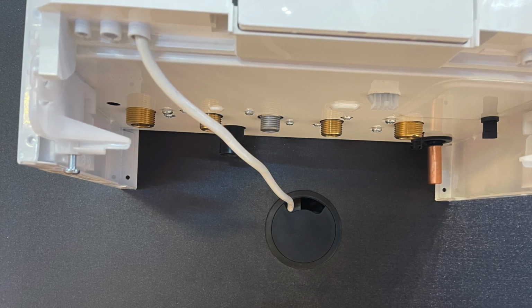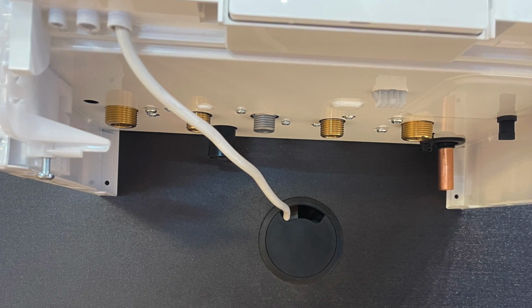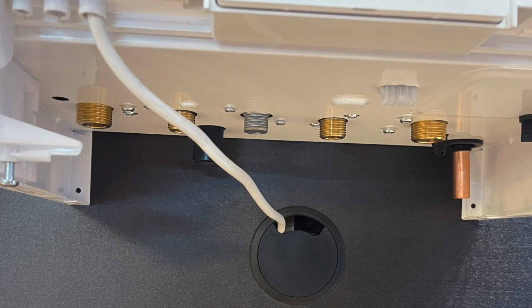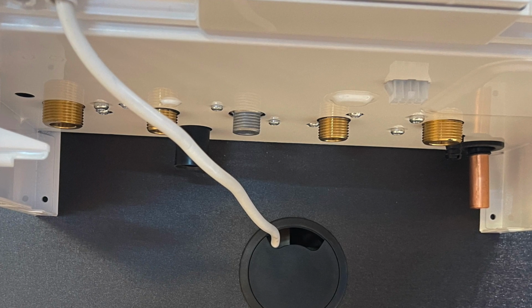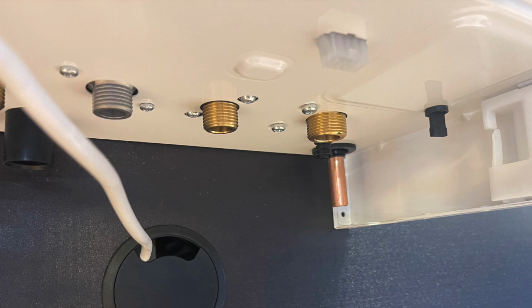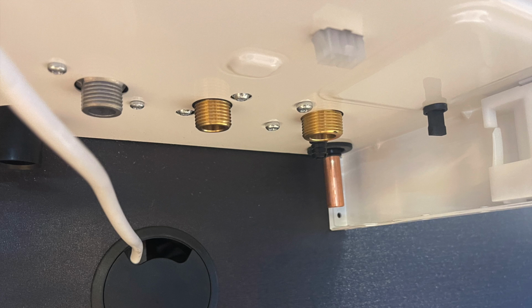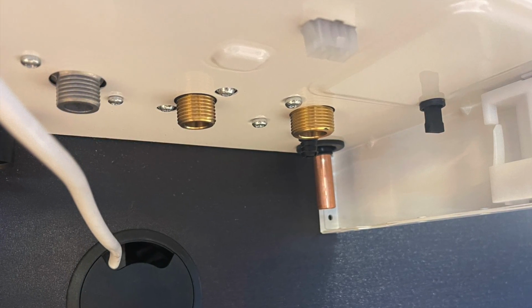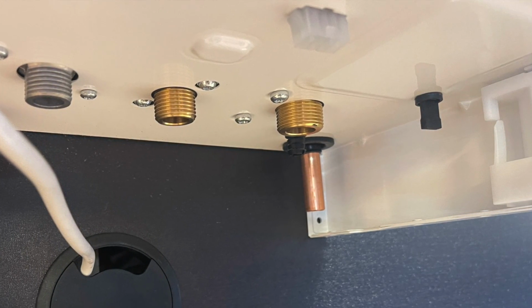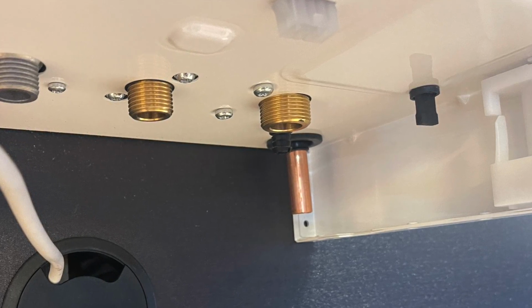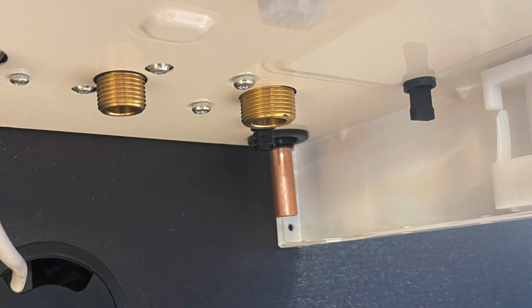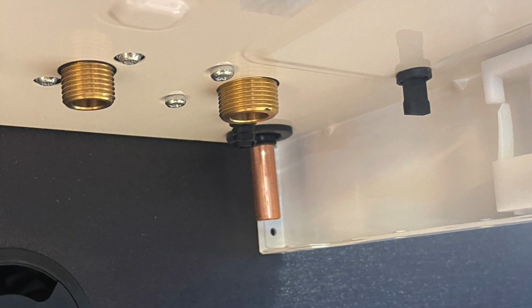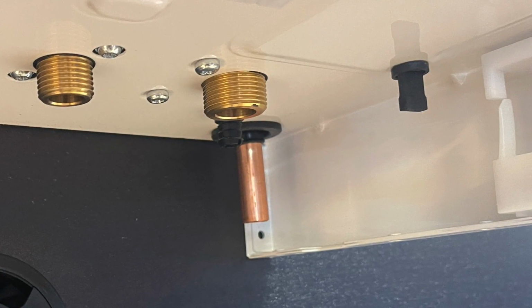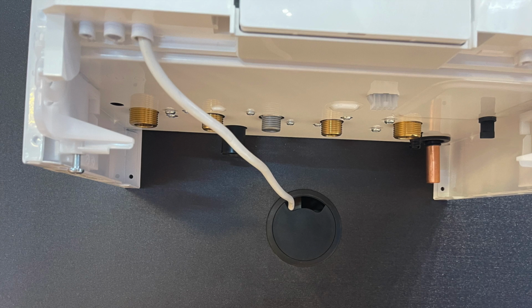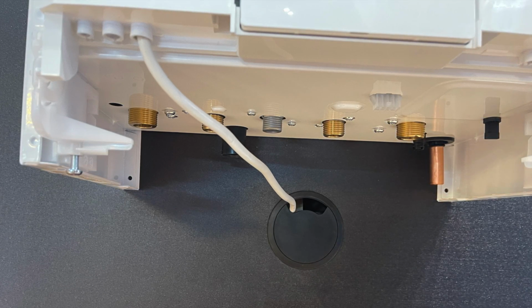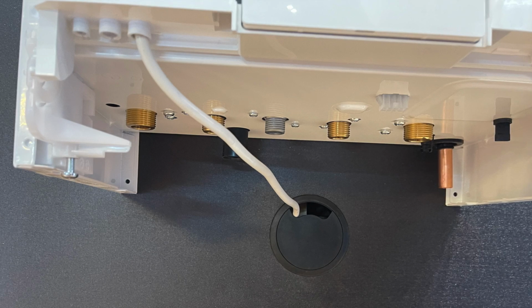If we have a look underneath, yes, you can still see the condensate pipe is still in the same place, but this pressure relief valve pipe is here on the right. Also, you can see the quick install and quick release coupling they've made has vanished, and it's gone back to just being a piece of copper. And now in the fittings pack, you get a compression 15mm straight connector, just like you used to in the first gen of the Logic boilers.